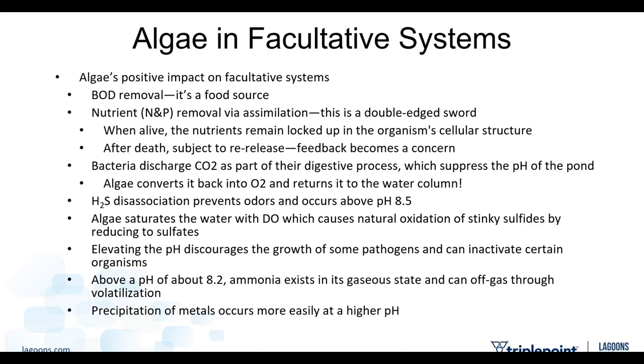You're getting natural oxidation of the sulfides by reducing the sulfates and less odors as a result. Pushing the pH up discourages the growth of some pathogens. It can inactivate certain organisms. And pH's impact on ammonia is really neat also. Above about 8.2 standard units, ammonia can exist in its gaseous state, and you can off-gas through volatilization. And then precipitation of metals. If you've got those metals in your ponds, they'll precipitate easier at a higher pH.